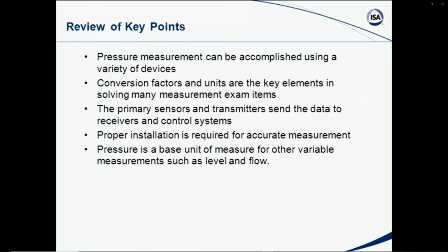So pressure measurement covers a lot of ground. It can be accomplished using a lot of different types of devices. Do you need that for local indication only? Is it going to be a transmitter? Is it a gas or a vapor? Is it liquid or steam? Where do I need to mount my transmitter? But also I have to know the conversion factors and units, and we'll be going over some of those as we go along in the measurement part of the seminar series.